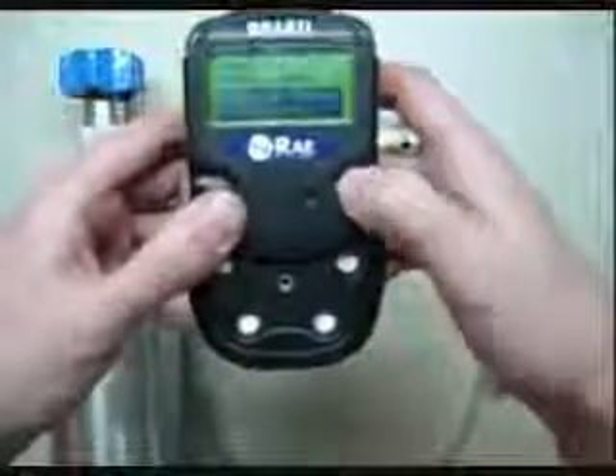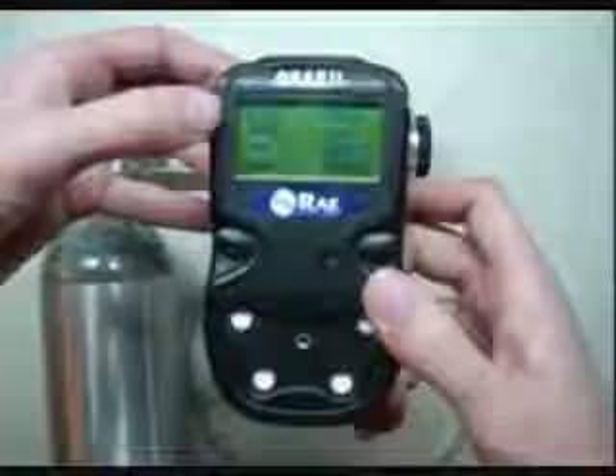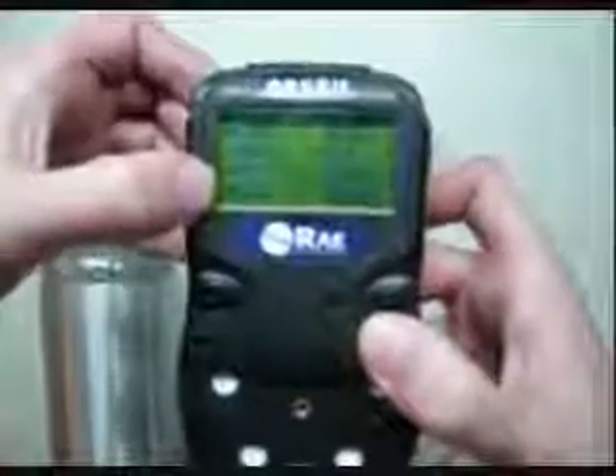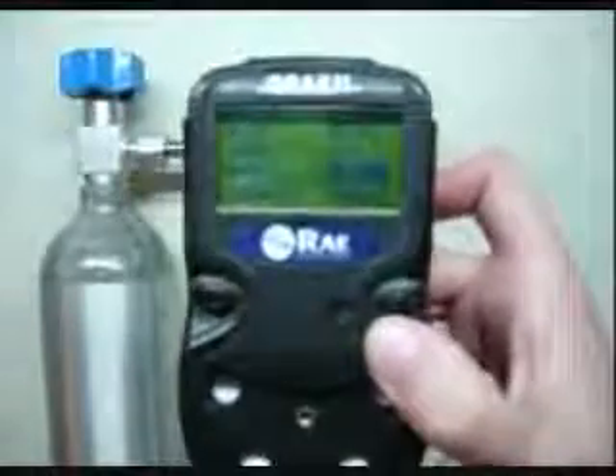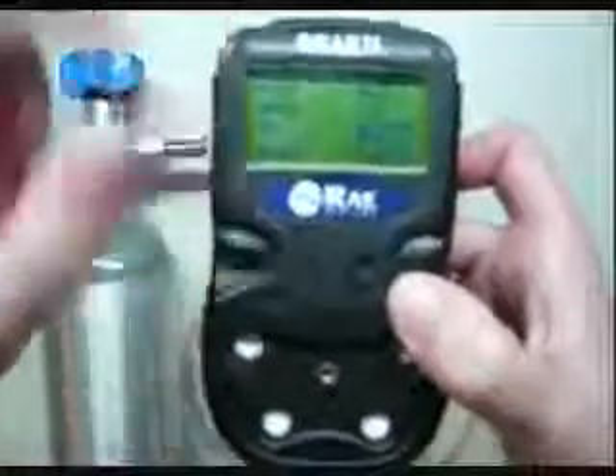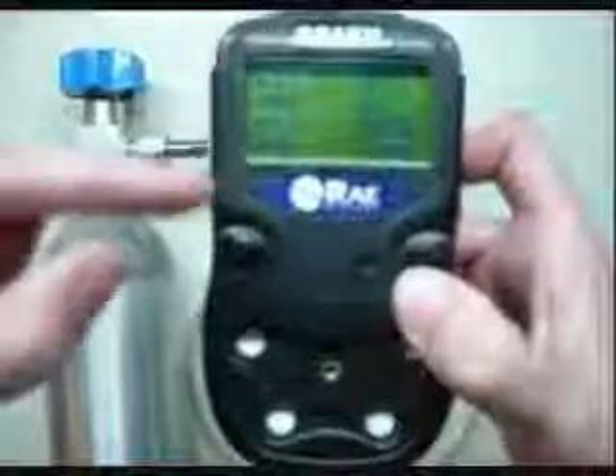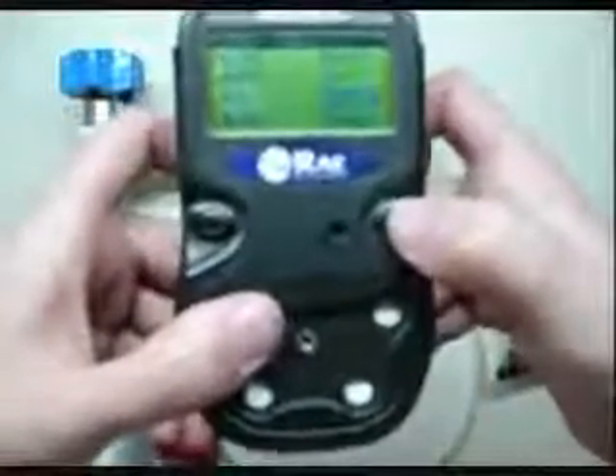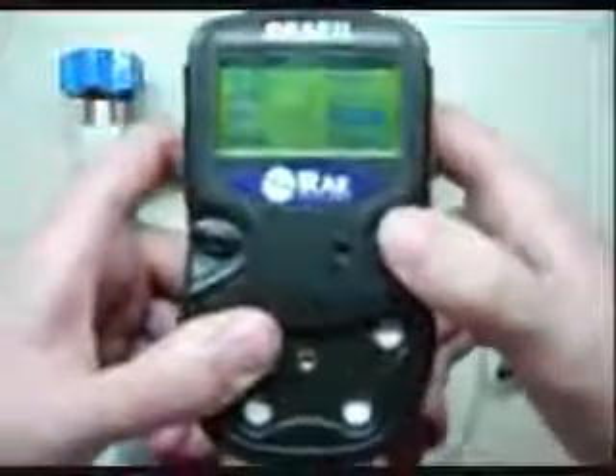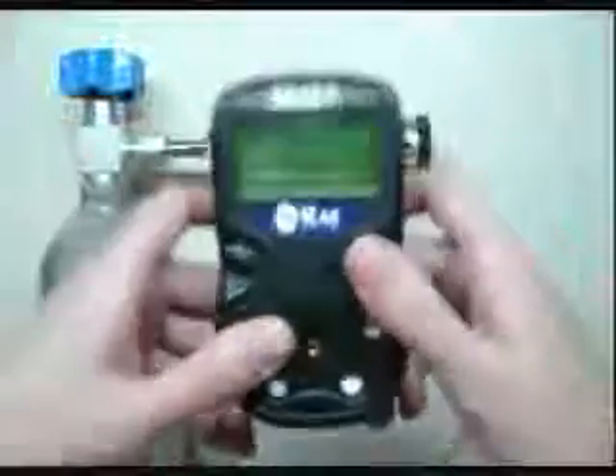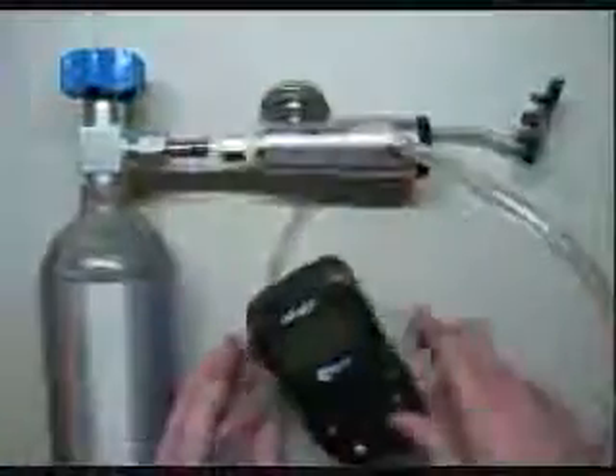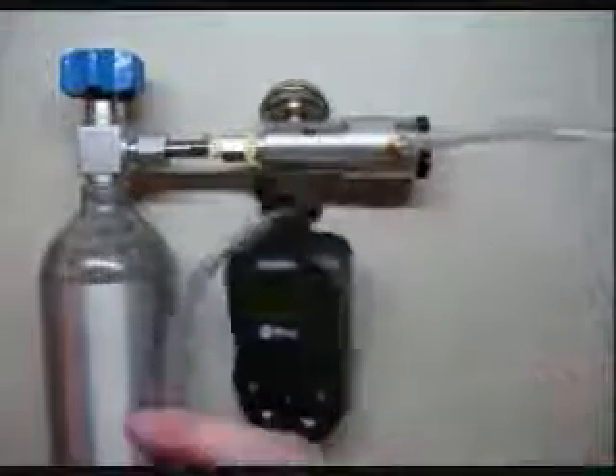Now it says here that it's all set, so we're going to hit yes on multiple sensor calibration. It'll automatically go down there. And you'll notice on the left here it has a star next to each one that it's going to calibrate. If you want to change, for instance, if you don't want to calibrate CO or H2S, press the button on the right and it'll move you down and then over. And then to remove the star or add it, you hit yes. So we're going to hit OK. And it says apply mixed gas. Apply the tubing here to regulate it. And if the unit says there's no gas flow like it does now, just let it be. It'll be alright.